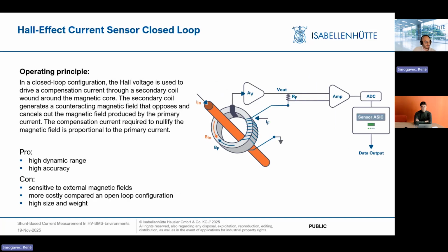There's also a closed loop version of that, which is similar in form factor but different in function, since it relies on a compensation current that runs through a magnetic core like before, until it nullifies the magnetic field going in the reverse direction, which originates from the conductor, the bus bar for example. It is way more accurate, and this reverse current, required to counteract the magnetic field, represents the current flowing through the conductor. But it's more expensive and it's prone to the same disadvantages as the open loop.